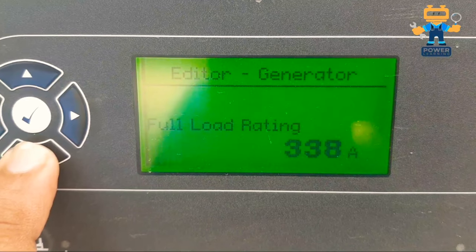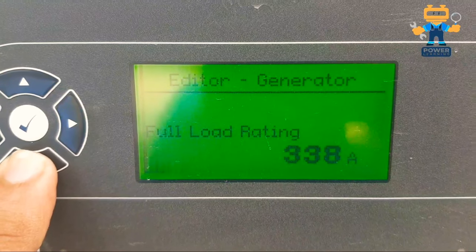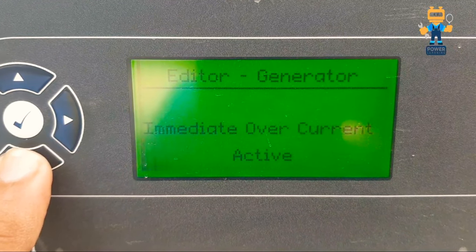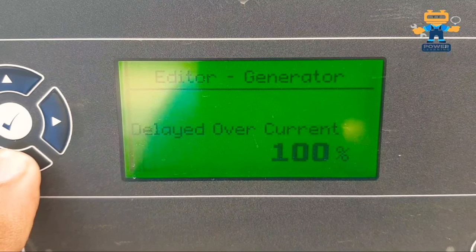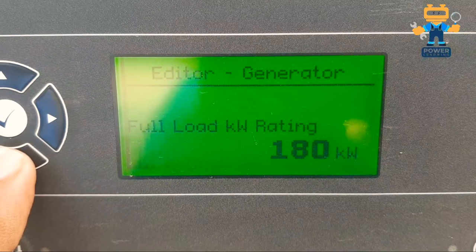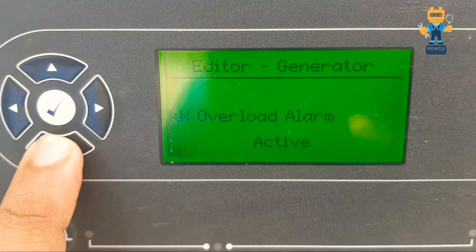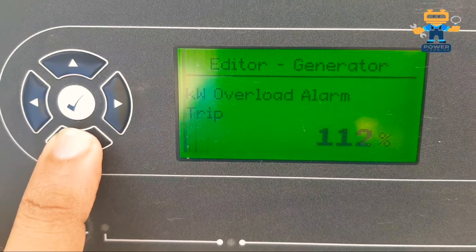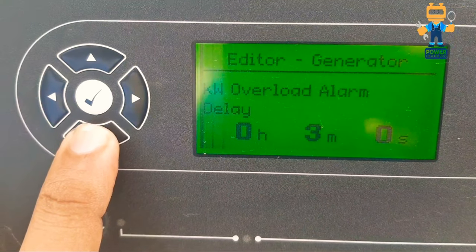Our CT rating is 400A primary and the full load rating is 338 amps. Delayed over-current is active, immediate over-current is also active, delayed over-current is set to 100%. Full load kilowatt rating is 180 kW. Kilowatt overload alarm, kilowatt overload alarm action, and kilowatt overload alarm trip are also configured here.